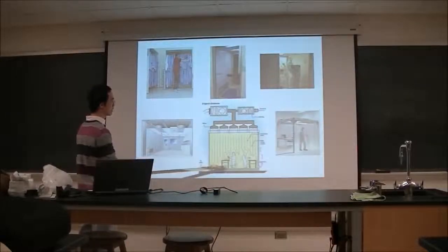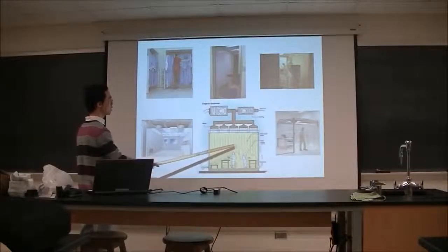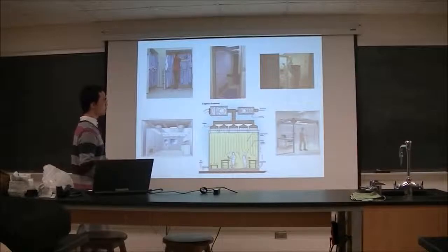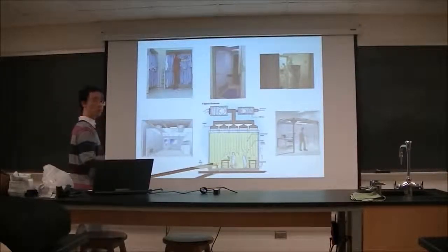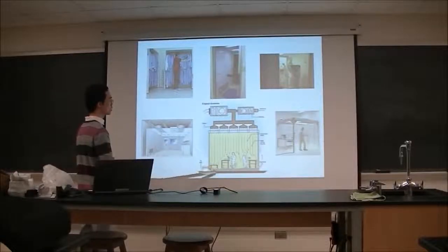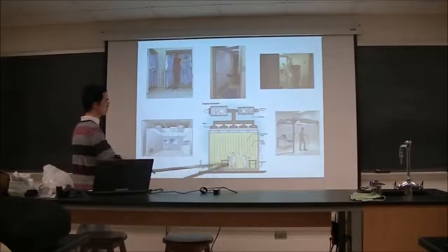So you have many particles here, and the purpose of this constant airflow is to keep a positive pressure in the room, so that no air from the outside can get into it. So only air from this room can get out. So it just blows away all the dust like this.